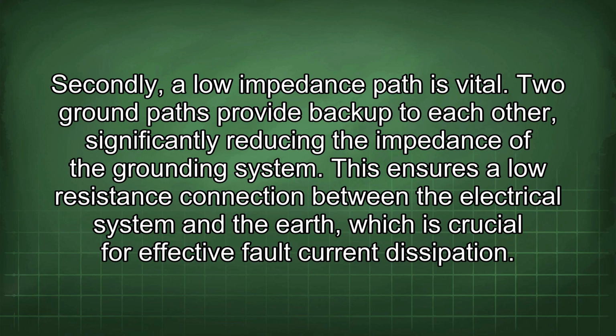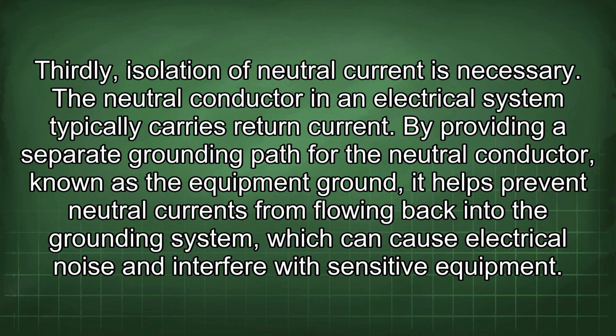This ensures a low resistance connection between the electrical system and the earth, which is crucial for effective fault current dissipation. Thirdly, isolation of neutral current is necessary. The neutral conductor in an electrical system typically carries return current. By providing a separate grounding path for the neutral conductor, known as the equipment ground, it helps prevent neutral currents from flowing back into the grounding system, which can cause electrical noise and interfere with sensitive equipment.